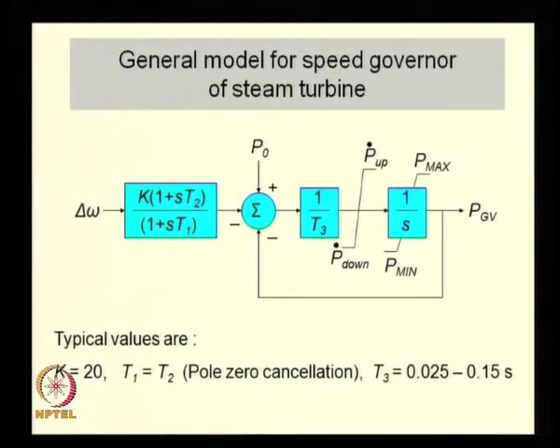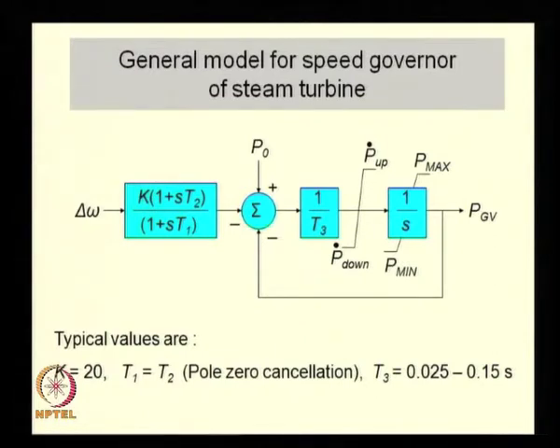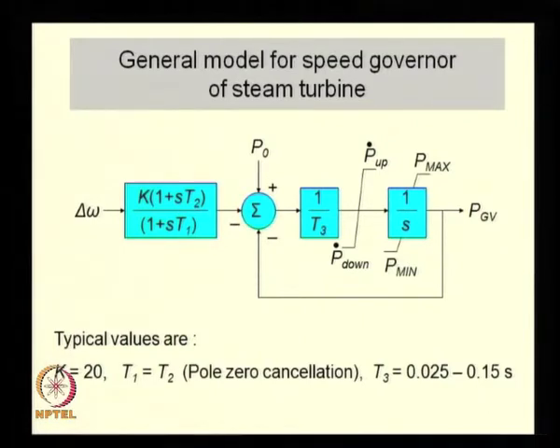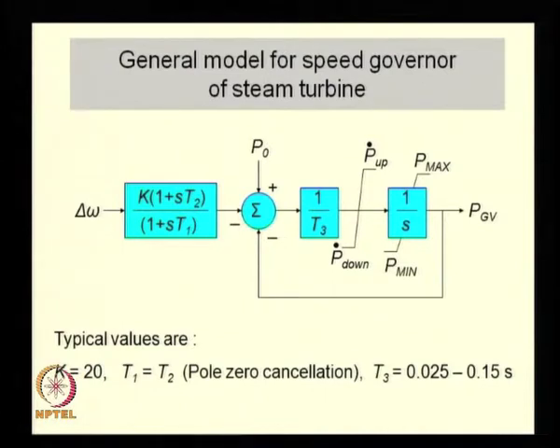One more model introduced here is a steam speed governor for a steam turbine. We are modeling the actuator as well as the speed governor control system. The gain of the speed governor is k. The model includes rate limiters — p_up and p_down — which come before the integrator and prevent the rate of change from exceeding the limiting values. PGV is the gate or valve position in per unit: a per-unit valve position of 1 means the valve is completely open and the machine will operate at rated megawatts.